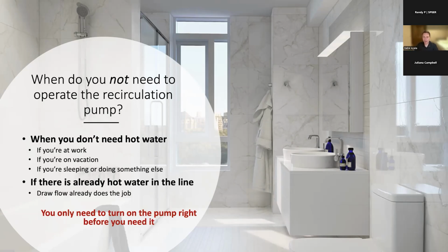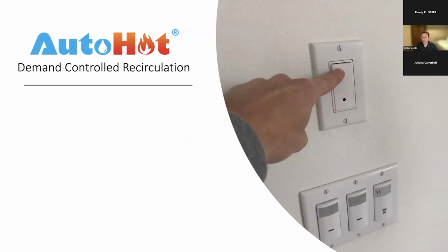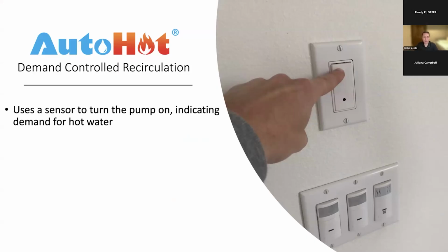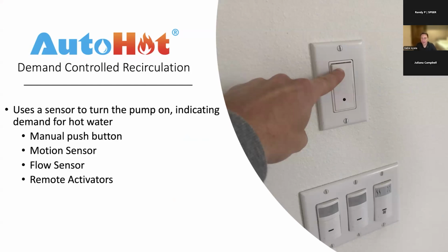So that's the concept of an on-demand or demand-controlled recirculation system, is that it uses a sensor or a switch to turn the pump on, which is indicating demand for hot water. And this can come in different forms. It could be a manual switch, a motion sensor, an occupancy sensor, a flow sensor, some type of wireless device, or voice activation. It could be something like, "Hey Siri, get me hot water." Anything that detects the presence or the demand for hot water within the occupancy.